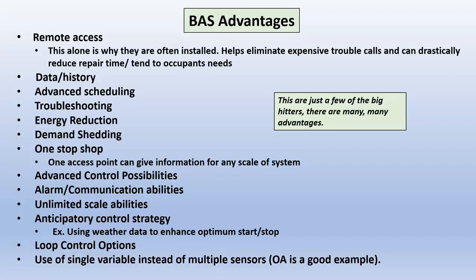There we go. These are a one-stop shop for information. If they're set up correctly, you should be able to get almost everything you need out of this system for troubleshooting. You have advanced control possibilities with the BAS that go far beyond what a programmable thermostat can do. And we'll talk about those a little bit more in detail. A lot of alarm and communication abilities.